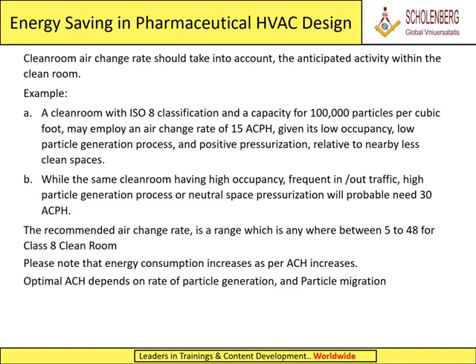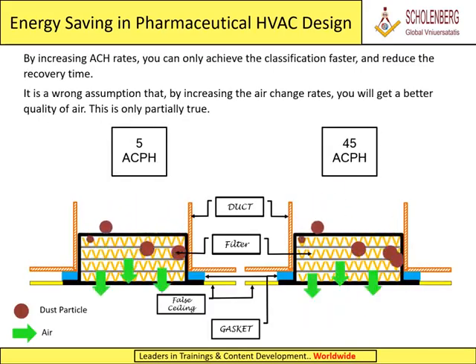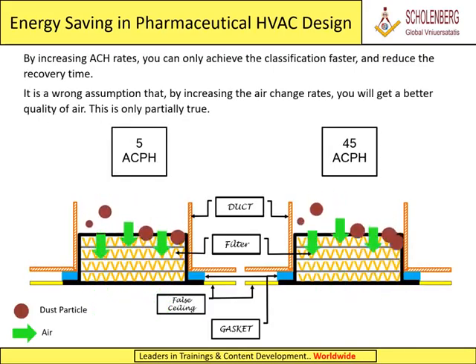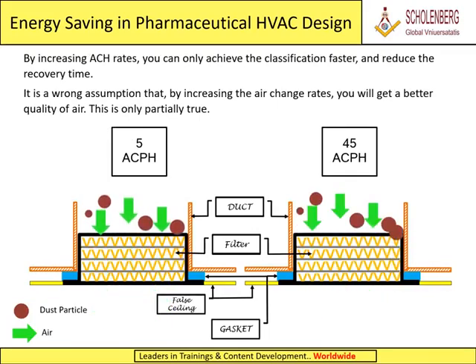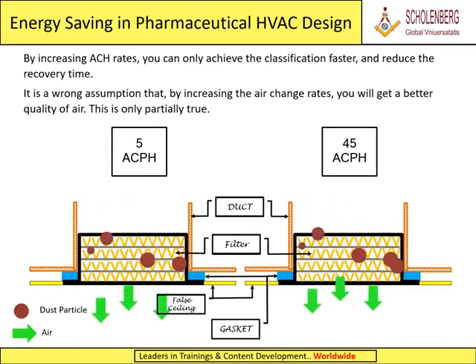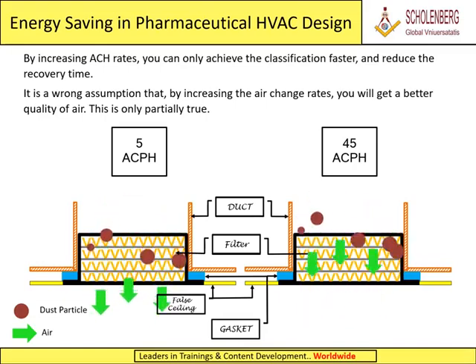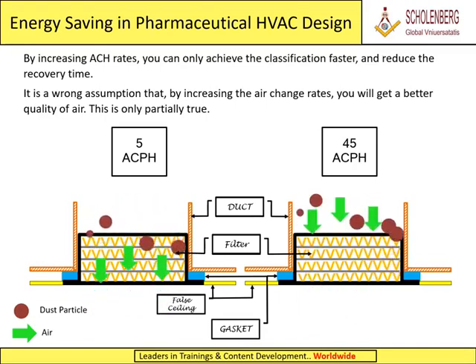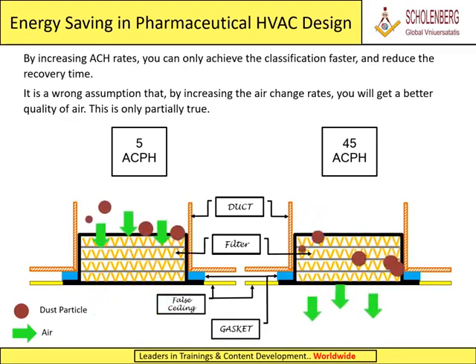The recommended air change rate is a range which is anywhere between 5 to 48 for a Class 8 clean room. Please note that energy consumption increases as ACH increases. Optimal ACH depends on the rate of particle generation and particle migration. By increasing ACH rates, you can only achieve the classification faster and reduce the recovery time. It is a wrong assumption that by increasing the air change rates you will get a better quality of air. This is only partially true.